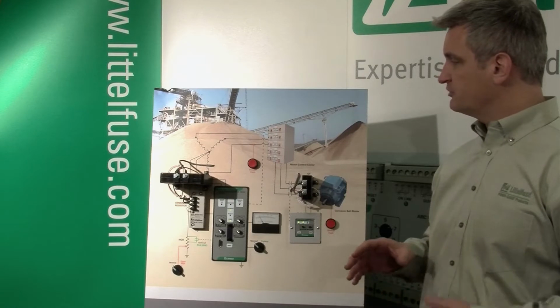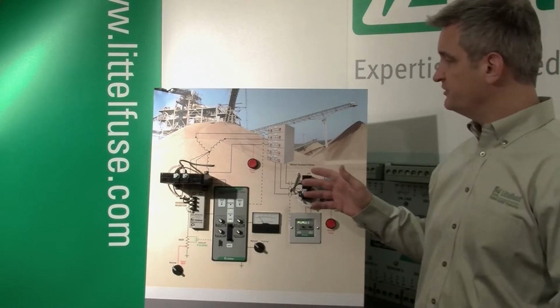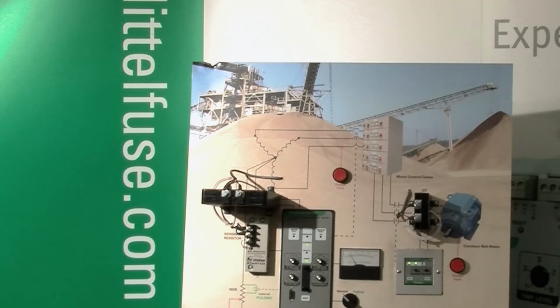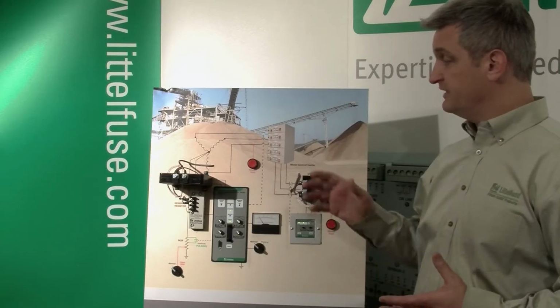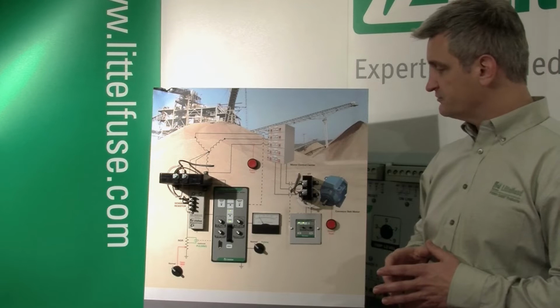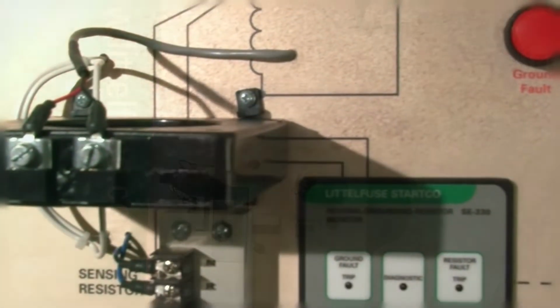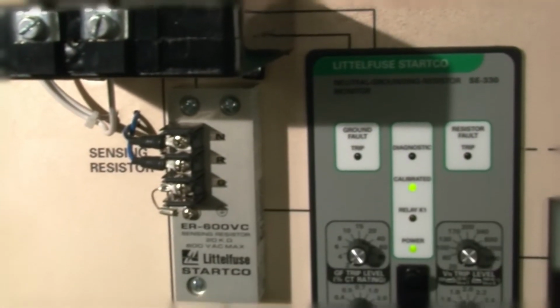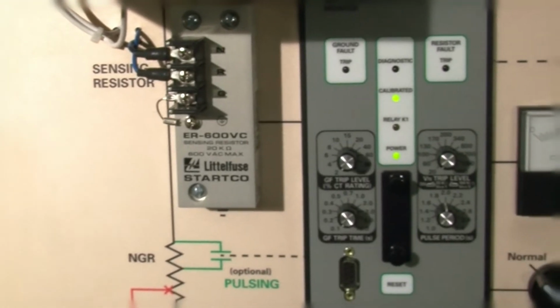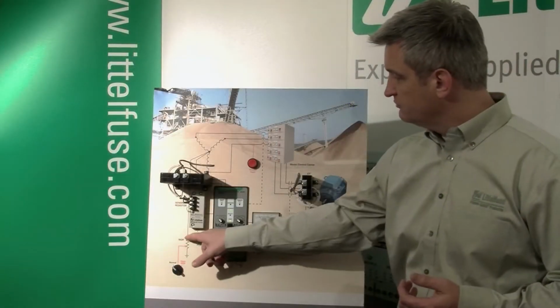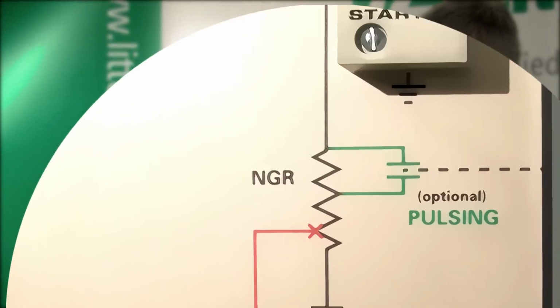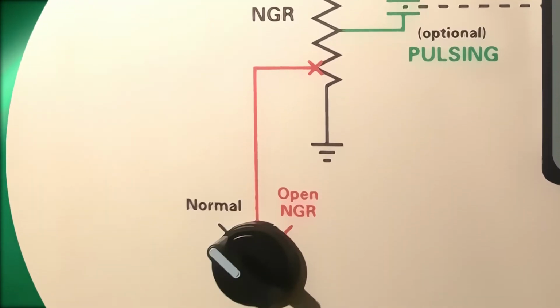Now, system grounding occurs at the source. So in our demonstration here, these three windings represent a generator or a transformer. When you put in system grounding, that's where it occurs. Resistance grounding, shown here on the board, is very simple. All it is is a resistor with two connection points. One goes to neutral, to the source. The second goes to ground. That's it. This is actually pretty simple.